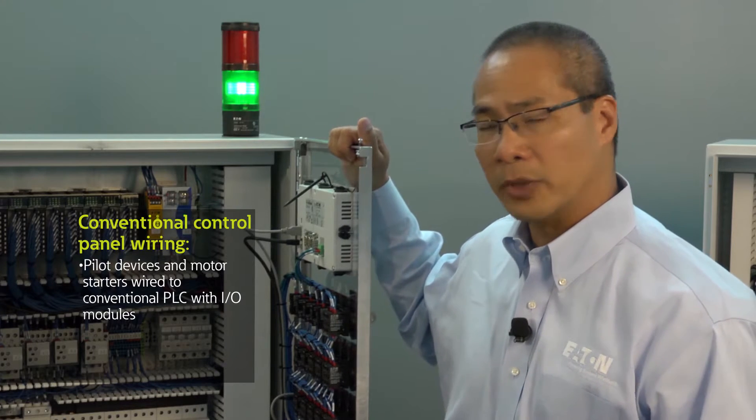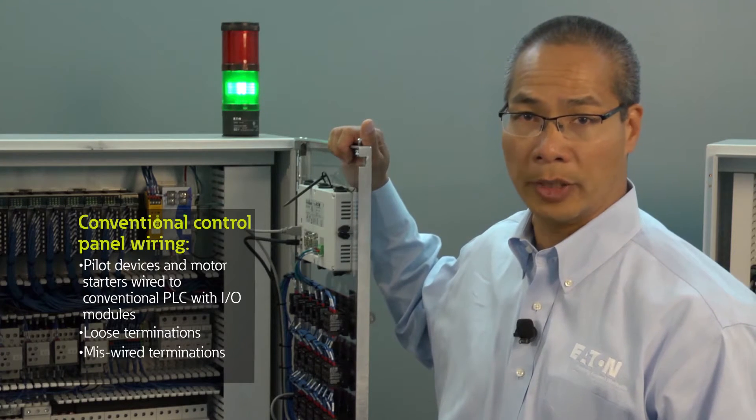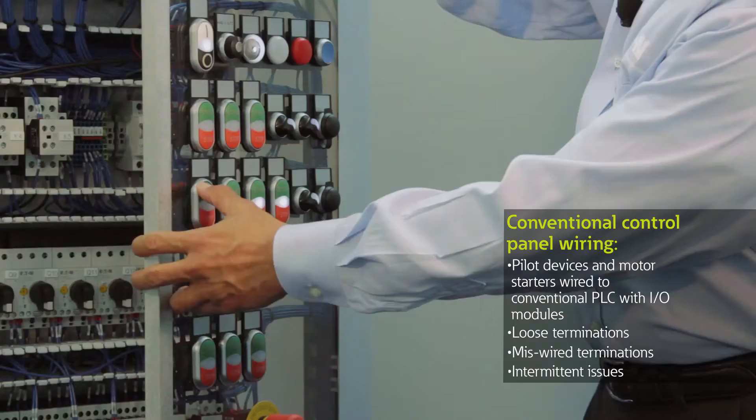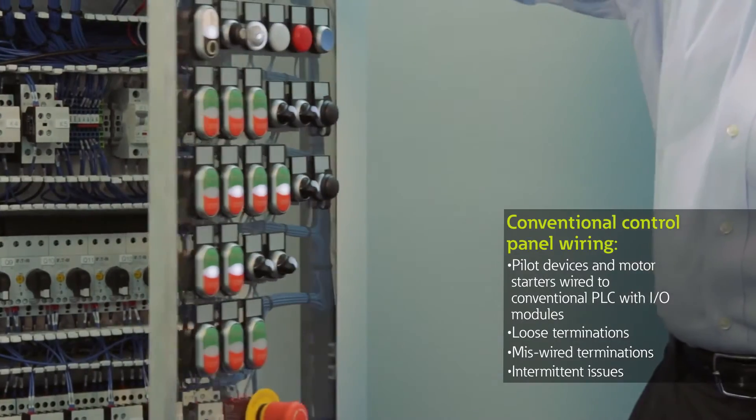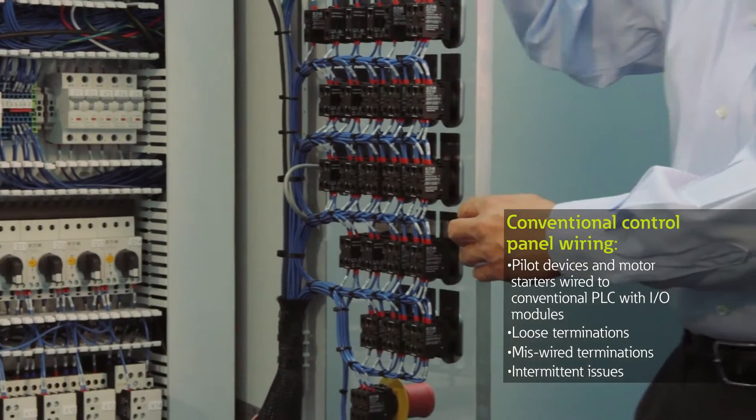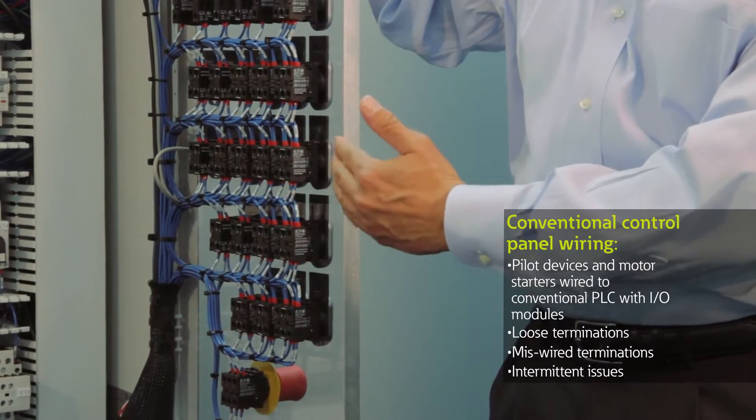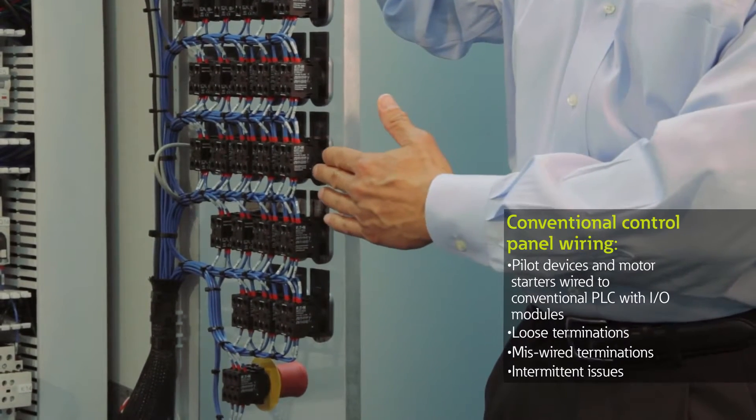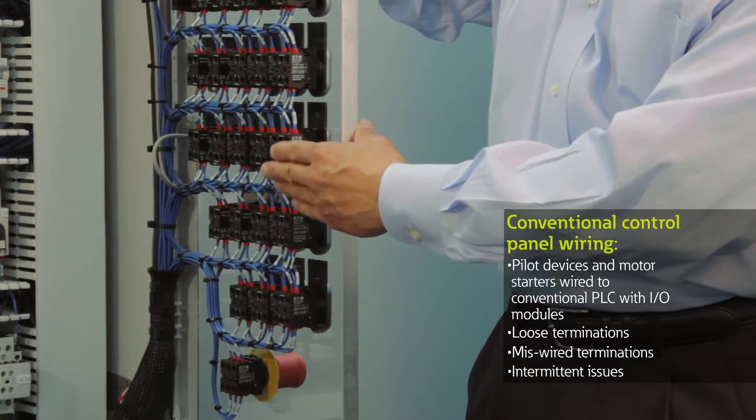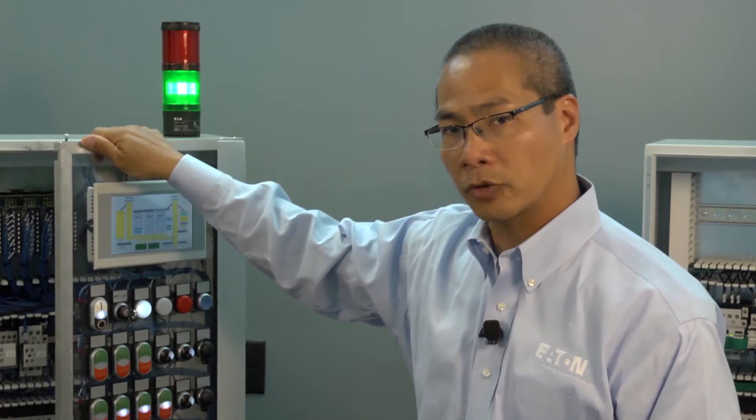We still have some problematic areas. We can have loose terminations, miswire terminations, and sometimes intermittent issues. As an example, on this particular control panel, I was demonstrating this and noticed that this light was flickering. What we later learned was that the wire was actually wired to the wrong side of the saddle clamp on the push-button contact block, but it was held in place very tightly because of the wire bundling. That sort of intermittent issue can be very time consuming to troubleshoot and identify.